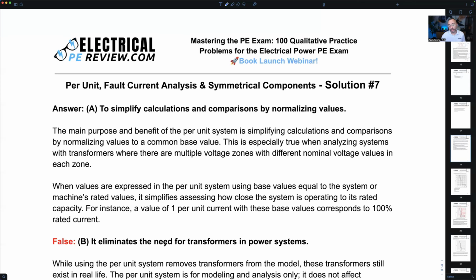the need for transformers in power systems, right? We still need them in real life, but it eliminates the changing of voltage and current with respect to the different voltage zones when we're looking at the model of our system, either on paper or on maybe a power flow study software. So it just makes it easy. I can compare apples to apples right away, and I can compare it to our chosen base values of the system instead of thinking like, okay, well, I've got 1200 amps here, but here's a transformer. And now we stepped up and I've got maybe 150 amps, but how does that relate to the 1200 amps? Maybe you have to work through this transformer and see what that value is. Is that backwards or forwards?